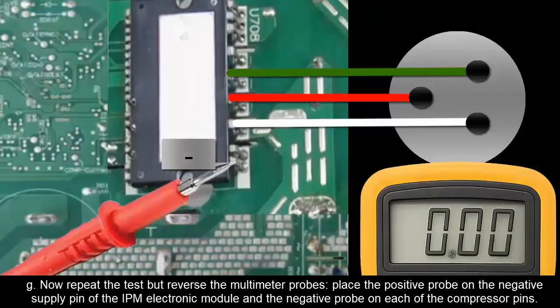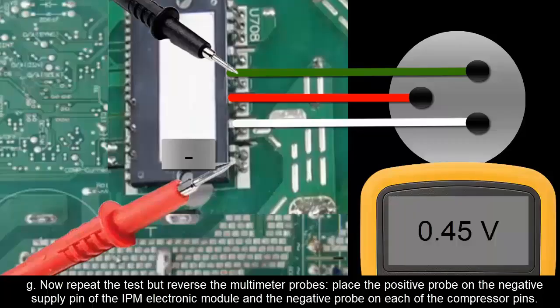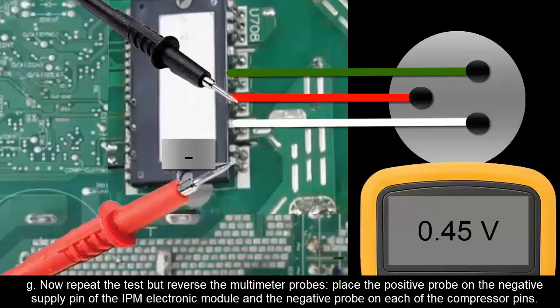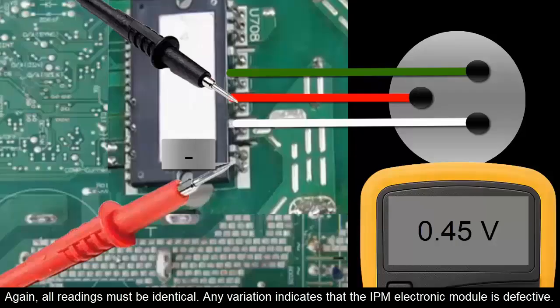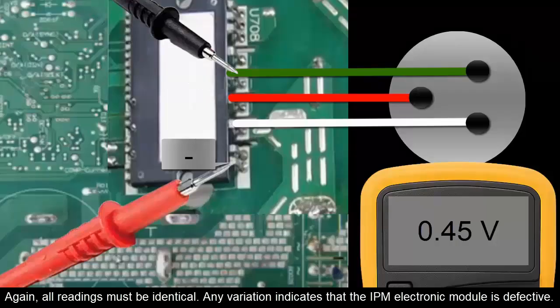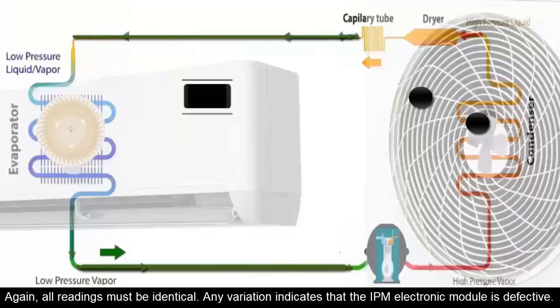G. Now repeat the test but reverse the multimeter probes. Place the positive probe on the negative supply pin of the IPM electronic module and the negative probe on each of the compressor pins. Again, all readings must be identical. Any variation indicates that the IPM electronic module is defective.